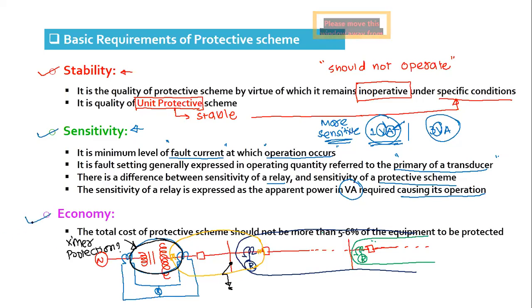And last comes economy. Already we have discussed that the cost of the protective scheme should not be more than 5 to 6% of the cost of the equipment which you want to protect. We have also considered some examples for this. Unless the equipment is very critical, generally the cost of protection is kept within 5 to 6% of the cost of the equipment. There are some exceptions, like in the case of generators or large power transformers, where the cost of protection can be more than this, depending upon their critical requirement in the power system.